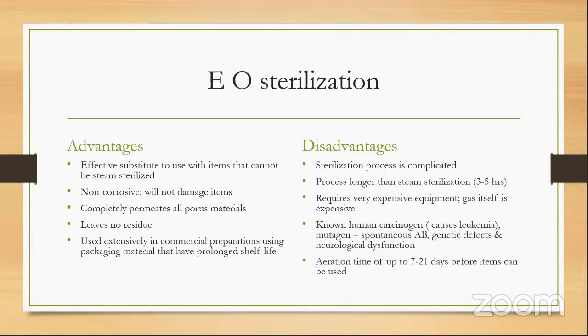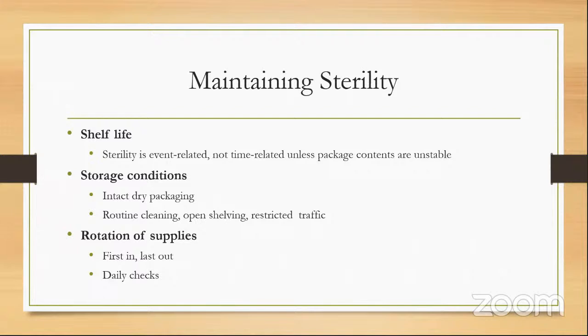The aeration time: because ethylene oxide gas permeates all porous material, all the packages that have been sterilized by this method have to be completely aerated. And they have to be aerated for a minimum of 7 to 21 days before the items can be used. We are not allowed to handle them. If you have to handle them, you have to be wearing PPE to protect yourself, including goggles, because exposure to the gas and the fumes can cause damage to your eyes as well. So it's very toxic. Like we said, it's a known human carcinogen.